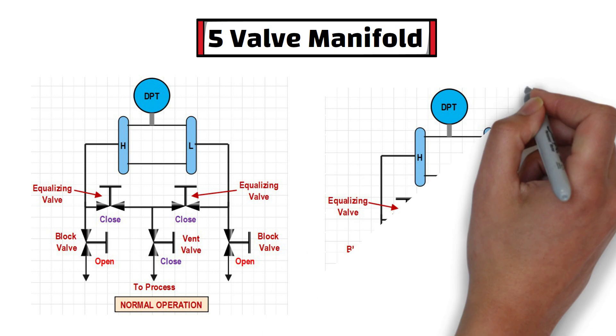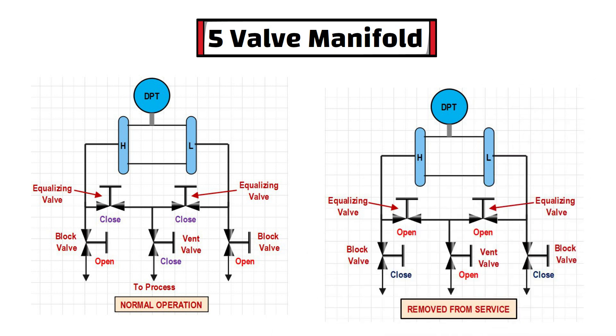On the other side, when DPT is removed from process for service purpose, both block valve is in closed position and both equalizing valve is in open position. At the same time, vent valve is in open position too.